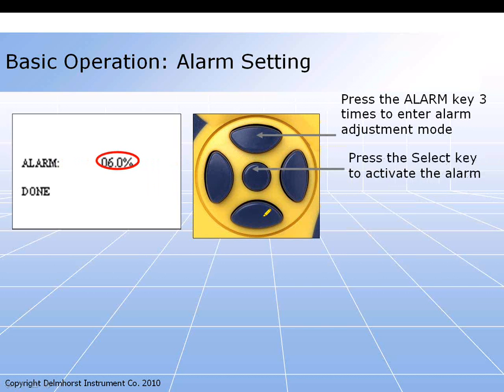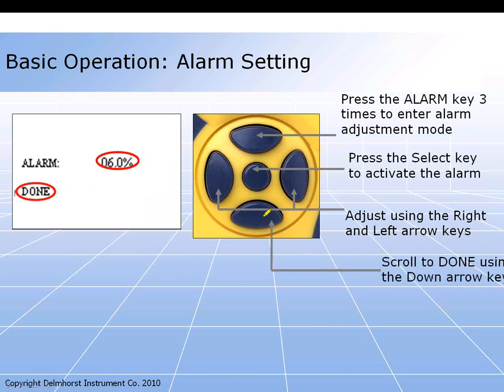If you press the select key, it will turn the alarm on. And then you can use your left or your right keys to go up or down scale to a higher or a lower moisture level. And then you just click on done or press select done to go back to the read screen, whether you're in pin or scan. I want to mention something about the alarm, again, that makes it unique when compared to other products in the industry.